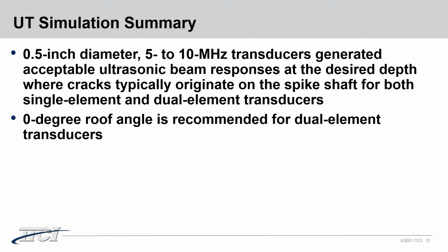Two key findings are summarized in this slide based on the simulation results. The first is transducers with half-inch diameter, 5 MHz to 10 MHz can generate acceptable ultrasonic beam responses at the desired depth. Secondly, for the dual element transducers, 0 degree roof angle is recommended.